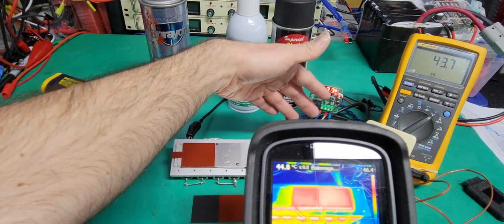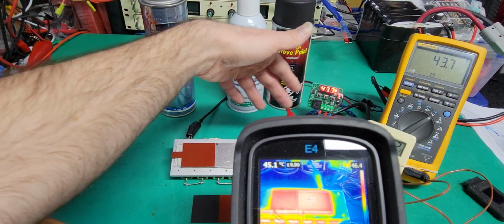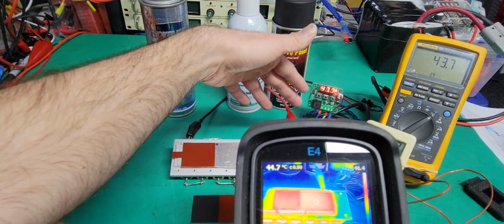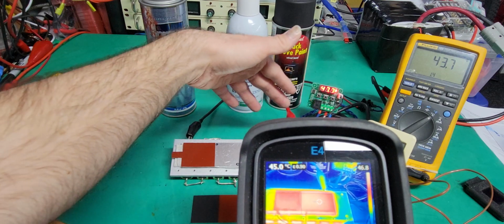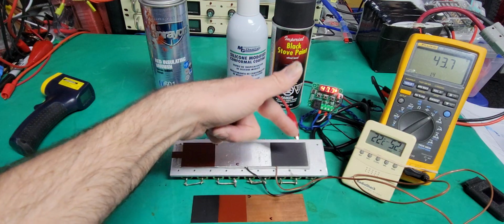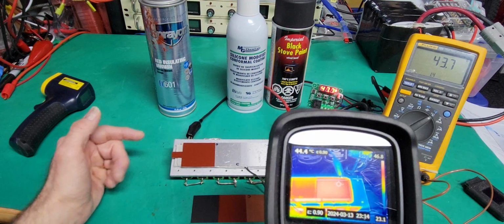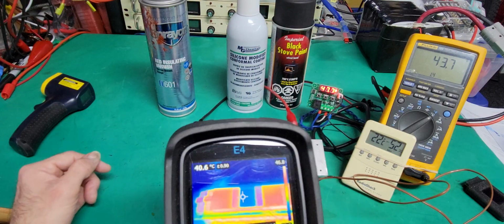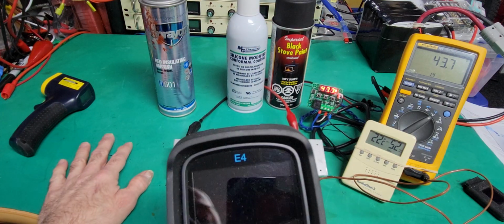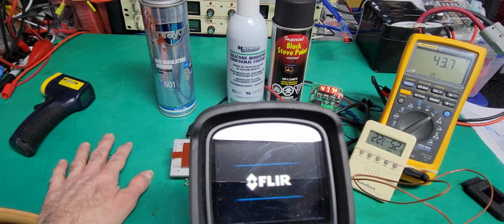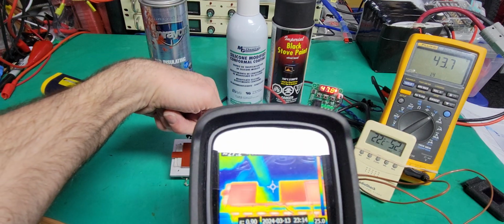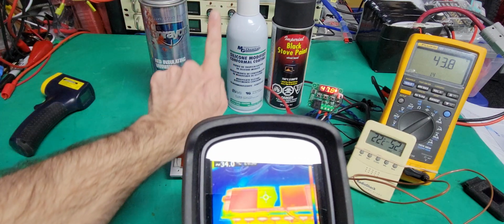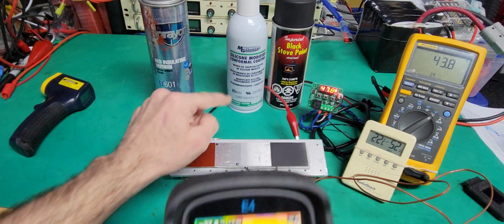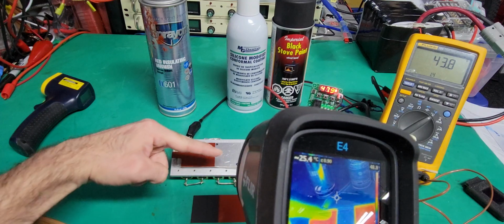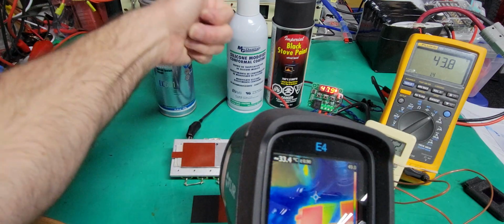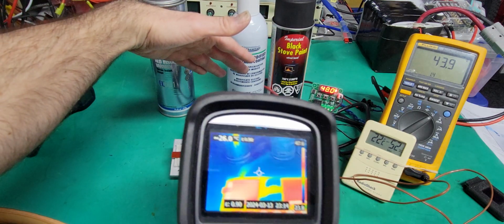But what happened on the black one? You see, you don't see any reflection, or if there's any, it's very, very low. So this color is actually helping to have great measurement and to get rid of any reflection, because if you don't pay attention to that, the temperature measurement that you will do with the camera will be from the reflected surface that is away from this one. So you see the camera will point right here and we'll see the temperature of the object right here, like you see in my hand here.